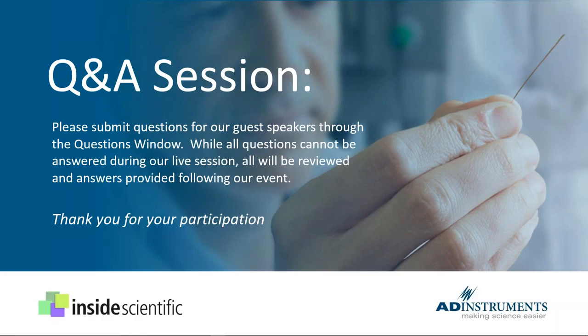Yeah, I don't know if Jim has any thoughts on this too, but essentially the answer is yes. We do recommend that you use heparin when you do the cuvette calibration. And that's just to prevent clotting, and what we essentially recommend is that you minimize the amount you use. Typically what we'll coach people through is to coat the syringe you're going to be capturing the blood with. And so you have a very small volume of heparin being added to the blood pool.